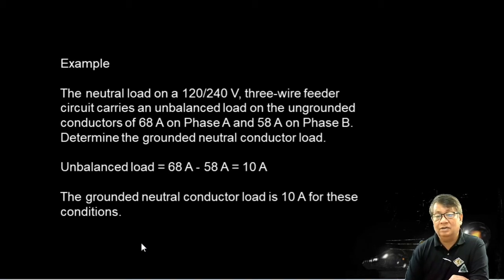So determine the grounded neutral conductor load. So unbalanced load, determine this one. We have the full load, the ungrounded full load of 68 amperes, and the grounded full load of 58 amperes, no? So we have this 10 ampere difference. Okay, so yun po, wag tayong magkumpiyansa kasi po yung 10 amperes ay masyadong malakas na yan for our body to resist the overcurrent, no?